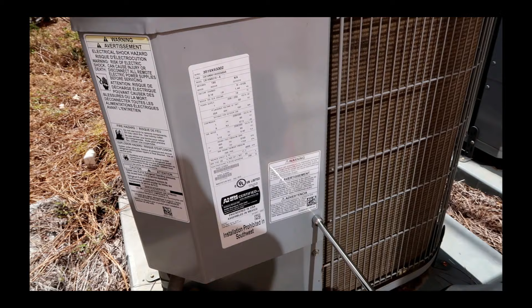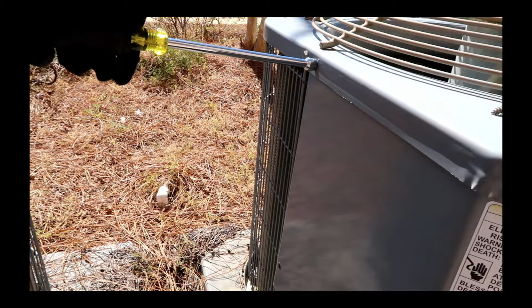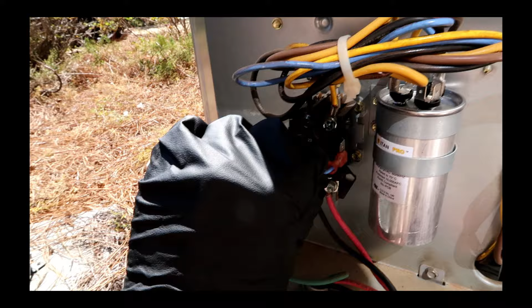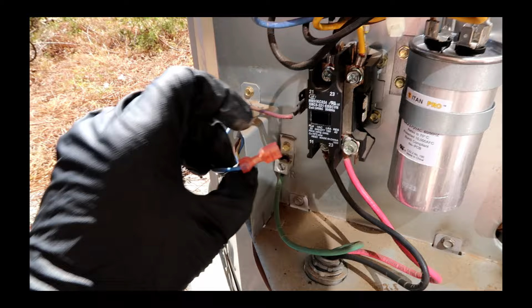Alright, let's check the old contactor on this thing. These carriers, man, full of drama. It's been a while since I've worked on the old school unit with the capacitor and the air handler. I've been doing the old modules with the fan motor, no capacitor, no fuse. Had to get my bearings on this thing. I think I got it now though. These carriers are notorious with these bad contactors and then popping the fuse or frying the transformer. So these contactors should ohm out around 19-ish, between 19 and 25 if I remember correctly.